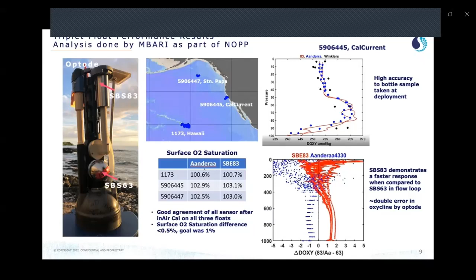If you look at the right panel, you see the results from the California Currents. And the top right figure shows the 83 data in red, the Aanderaa in blue, and the Winklers in black. And if you compare the Winklers to the 83 and the Aanderaa, we get high accuracy between the bottle samples at the deployment site. And this was good news to us as well. Then finally, we did an analysis of the response time of the sensor. And you can see when comparing the response time of the 83 to the 63, it's faster than the Optode. And we can tell this by there's about double the error in the Optode to the 83 in the oxycline on this particular float.